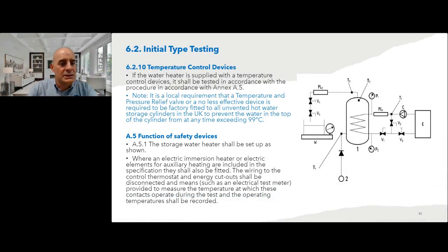6.2, so 6.2.10, is the temperature control devices. So if the water heater is supplied with a temperature control device, it should be tested in accordance with the procedure in Annex A5. So note, it's a local requirement that a temperature and pressure relief valve or a no less effective device is required to be factory fitted to all unvented hot water storage cylinders in the UK to prevent the water at the top of the cylinder from at any time exceeding 99 degrees.